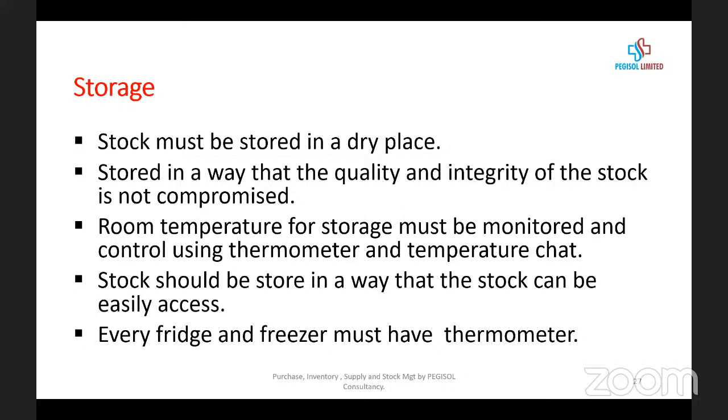Room temperature for storage must be monitored. So where you keep your reagent, you must put a thermometer, and that thermometer must be calibrated. You must fill in the log chart of that thermometer to check the temperature. Some of us who don't care just put stock anywhere. Stock should not be dropped anywhere. Even when it is in the lab, ensure that where you are putting it is a controlled environment, an environment that can be controlled, where you can use a thermometer to measure the temperature, adjust it, and take corrective action in case of deviation and the rest.